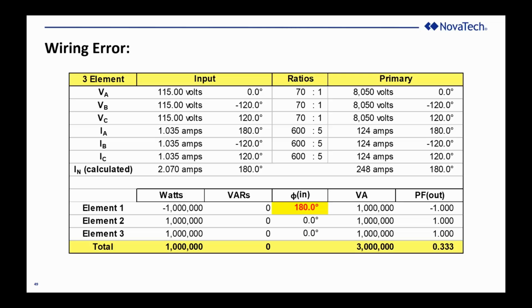So if I were to type in a bias of 180 degrees on the A-phase current, I know that lines up with element 1 watts. That's not the point. The point is that this little phi-in cell is added into the current for A-phase current in the upper half of the page. So I don't have to change the relationship between the A-phase voltage and the A-phase current except the bias of 180 degrees, which is the result of having wired it backwards.